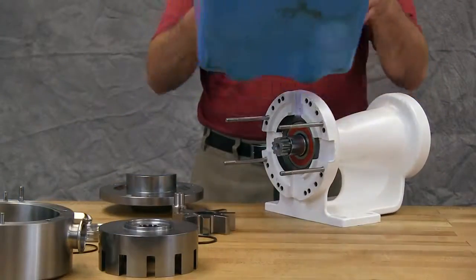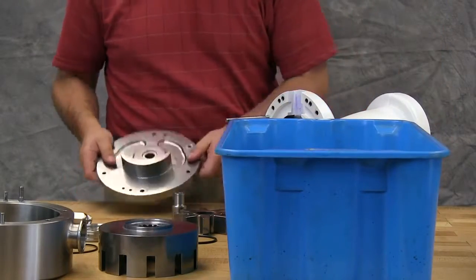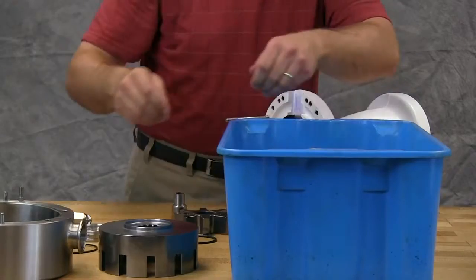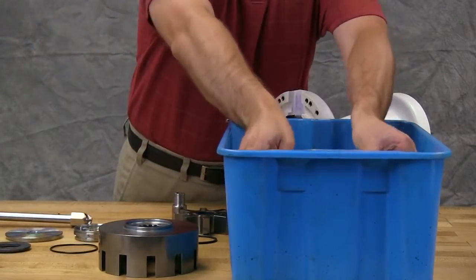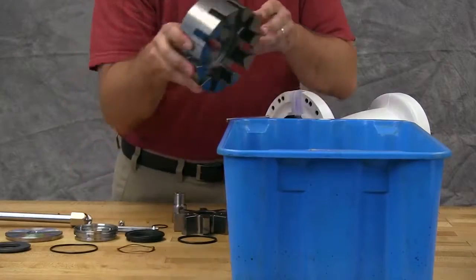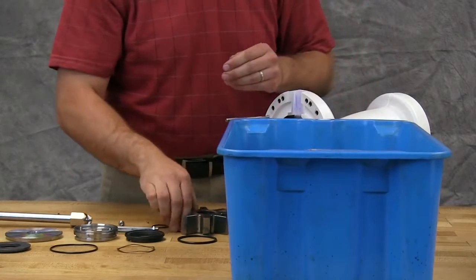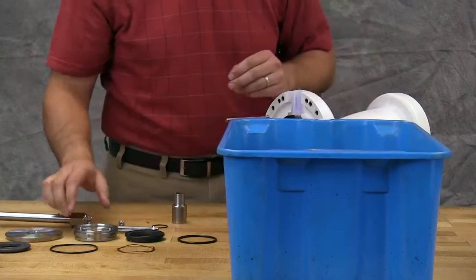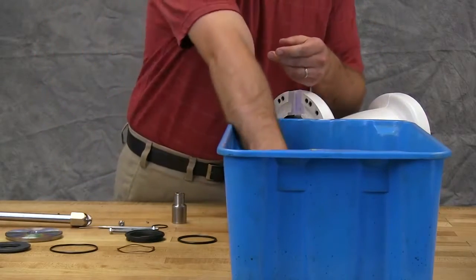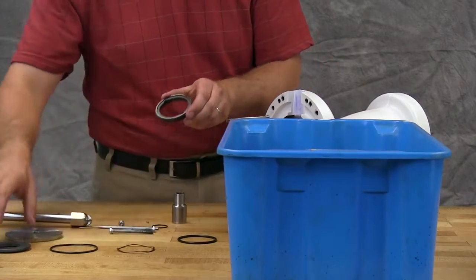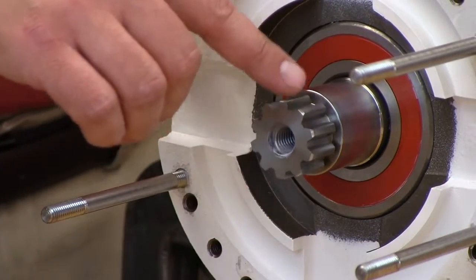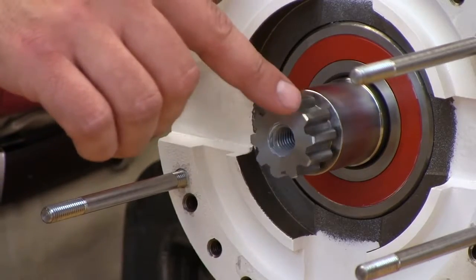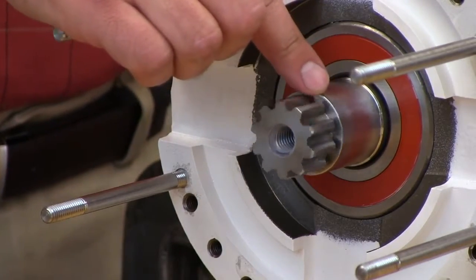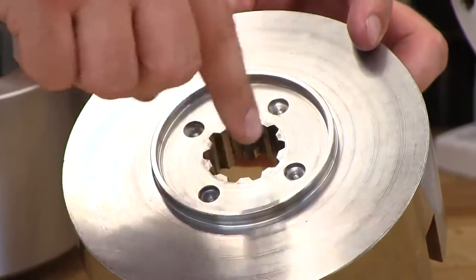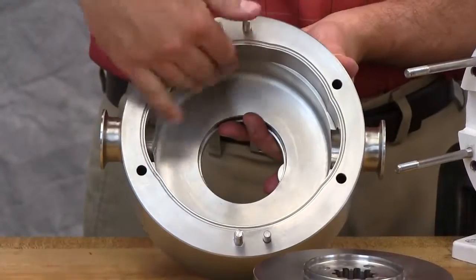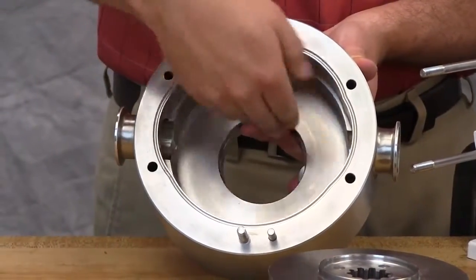Once the pump has been disassembled, submerge and soak wet end components in a clean out of place tank with a suitable cleaning solution. Ensure that the cleaning solution is compatible with the pump components. Pump parts should remain in the cleaning solution no longer than necessary to ensure adequate cleaning in order to avoid corrosion to pump components. After cleaning the pump components, inspect pump parts for wear. If the spline area of the rotor or shaft is worn or damaged, replace the part. If the shaft shoulder next to the spline area has a sharp edge, use a fine emery cloth to remove the sharp edge to avoid damaging the seal.